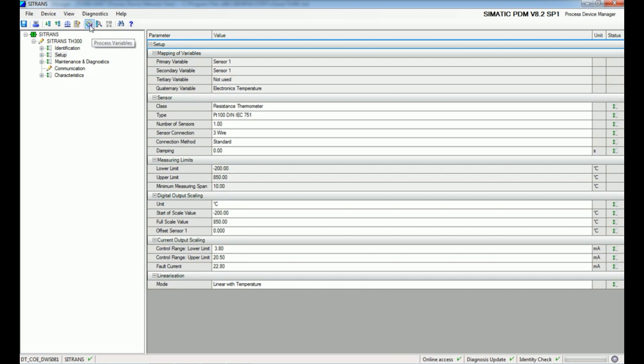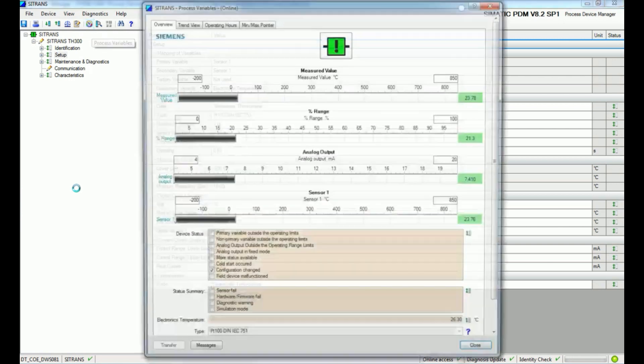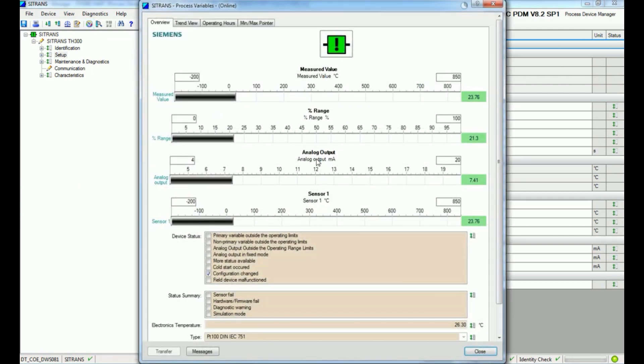We will close this window — we have successfully completed parameterization with the HART modem. Now I will open Process Variable and from there we will get detailed information about the analog input. We can see the measured value range in percentage, analog output in milliampere, and sensor data. Right now we are getting a temperature of 23.76 degrees Celsius and an analog output of 7.41 milliampere.